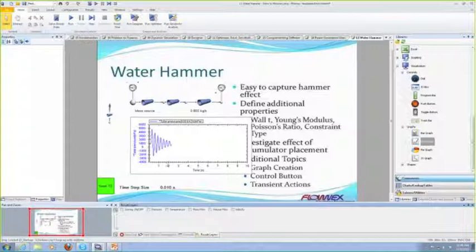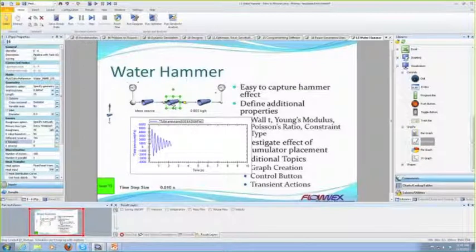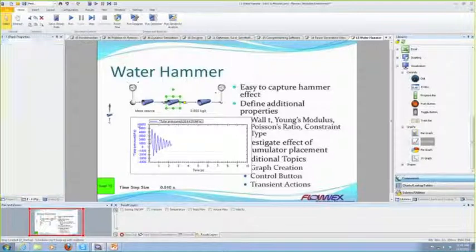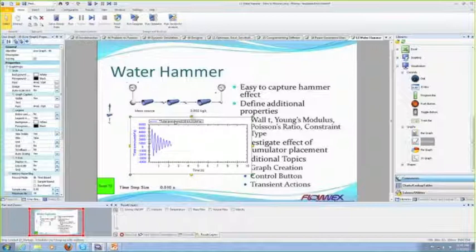And so, we can capture this type of event, but if we actually wanted to track how much liquid goes to vapor or anything like that, we could apply a two-phase material model to this and actually track quality versus time. And so what we see here is we get these huge pressure spikes. And so we're going to play around and just insert this accumulator.